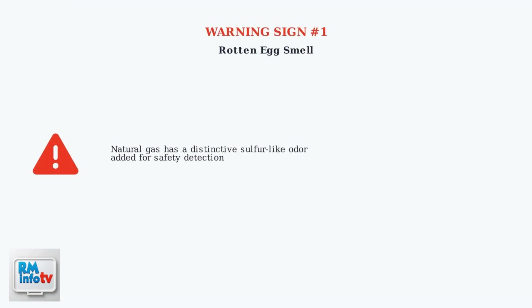The first and most recognizable sign of a gas leak is a distinctive rotten egg odor. Natural gas is naturally odorless, but utility companies add a chemical called mercaptan to give it this unmistakable smell for safety purposes. Another warning sign is sound. You may hear hissing or whistling noises near your water heater, which indicates gas escaping from pipes or connections. This sound is often accompanied by the smell of gas.